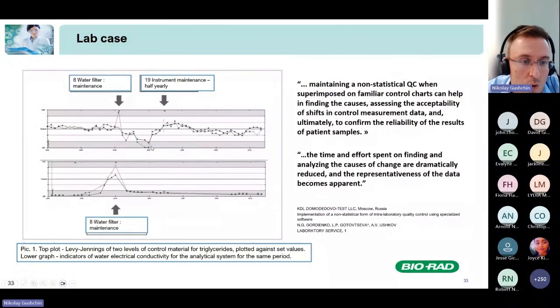So the instrument was also contaminated with this bad water. First of all, they changed the water filter, but this didn't help with the instrument results. So they decided to stop testing on this instrument and do the half-year instrument maintenance. After that, the results came back to normal, and they continued patient testing. This is just an example of how multi-Levey-Jennings charts together with actions and comments can give you a clear picture of what is going on in a lab, help you quickly troubleshoot, and give you full traceability. For example, if an audit came to the lab and found this shift on the Levey-Jennings chart and asked what happened, you would be able to explain the situation very quickly with all this additional information.